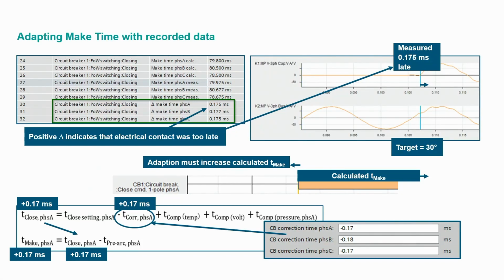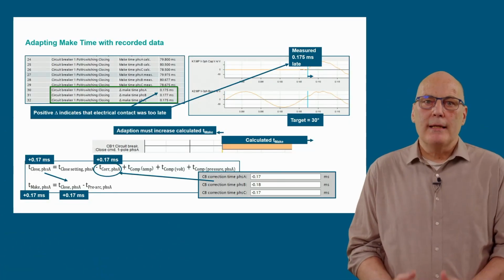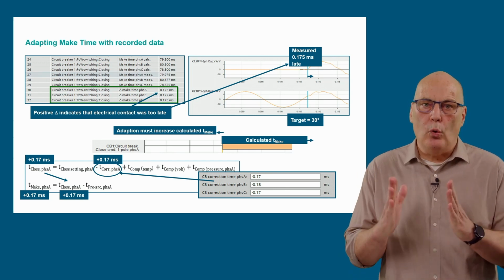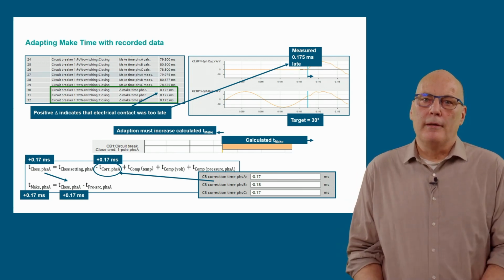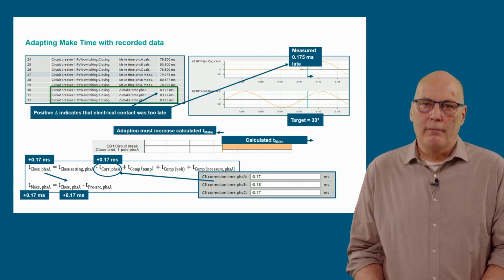The make time can be adapted to compensate for the observed delta. This is done with the correction time, as shown in the settings at the bottom right-hand side. A positive delta make time indicates that the close was too late. Here, 0.175 milliseconds too late. If the make instant is too late, the close was issued too late. This means that the calculated closing time was too short. It must be increased by the delta make time of 0.175 milliseconds.